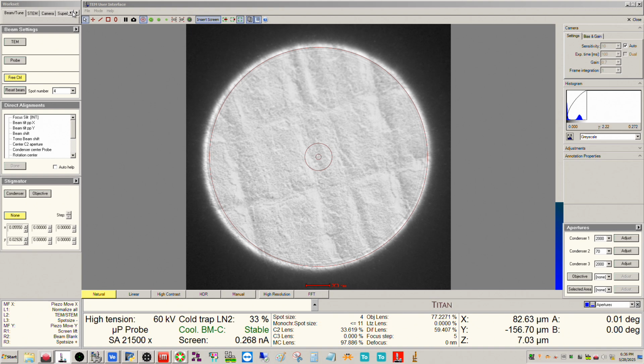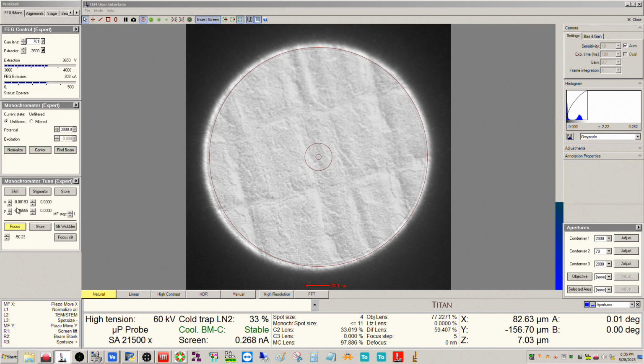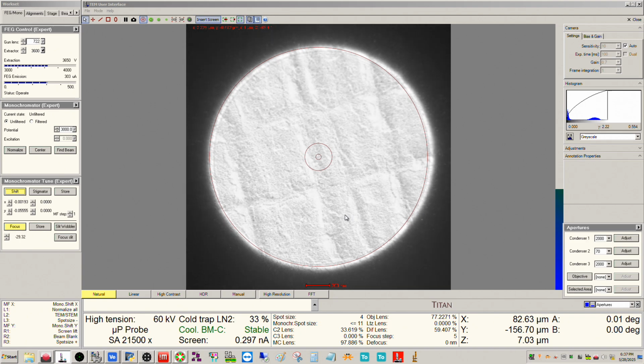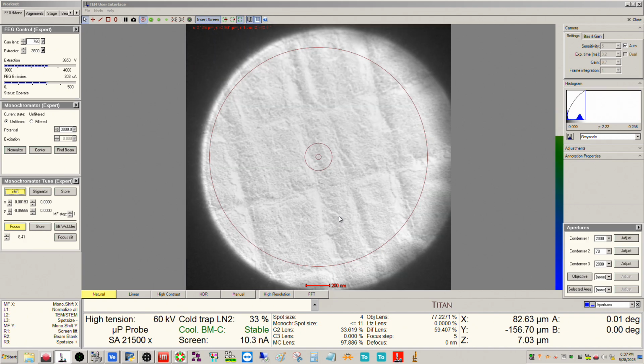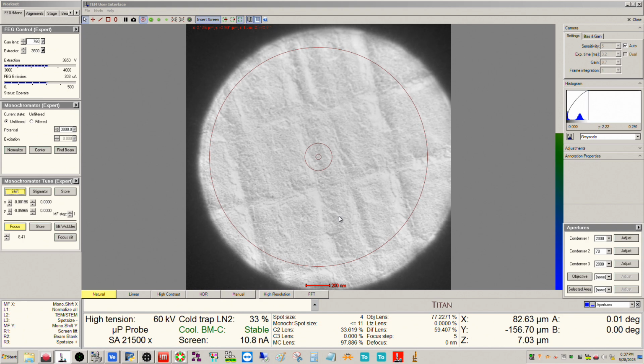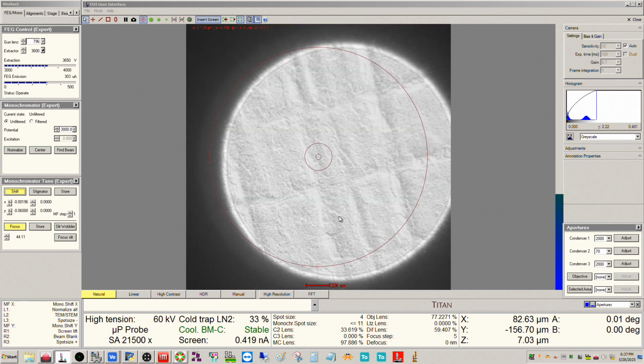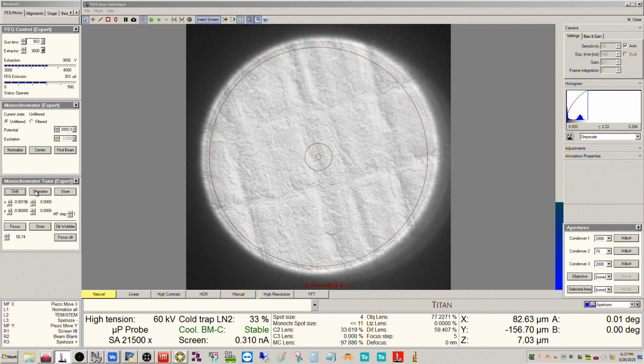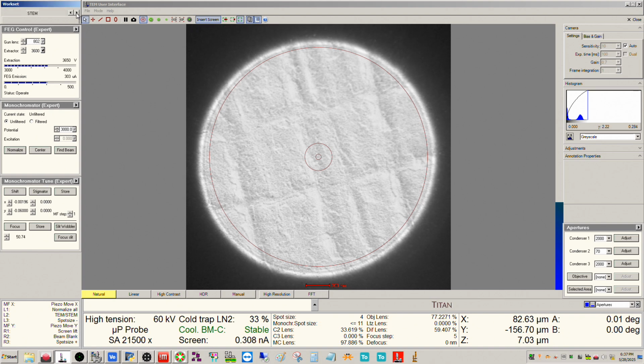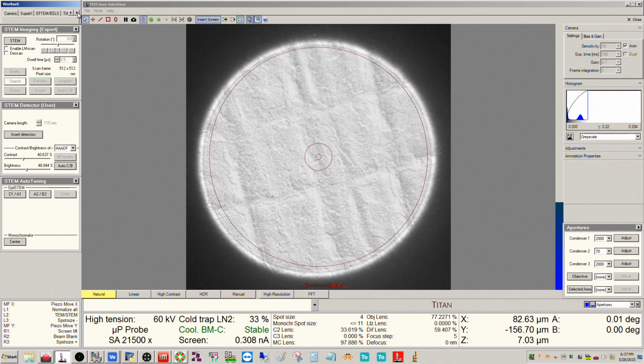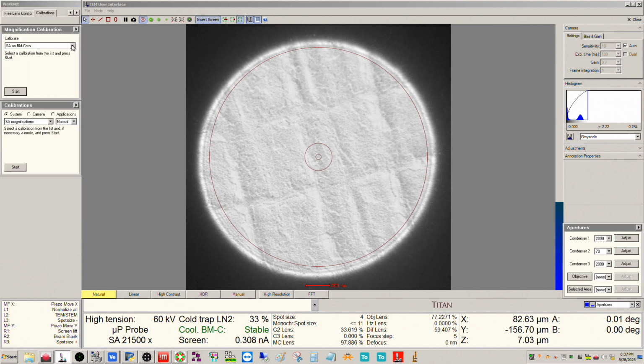Okay, so now I'm going to put the mono at negative initially here, and when we need to switch that back for doing microprobe, we can do that, okay? But just to start with, I'm going to put that at positive because that's what we typically do when we're doing STEM. What I'm finding here at 60 kilovolts is I'm making the extremes a little bit higher, plus or minus 50 actually, because otherwise I'm seeing the beam not fully illuminating the aperture rim. All right, so we are good there, and so now we can go into calibrations, find our Microprobe STEM calibration, and click Start.